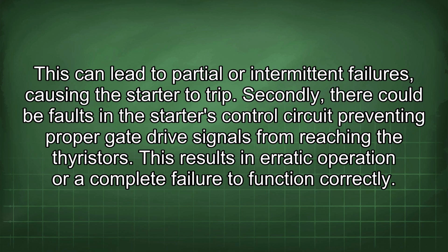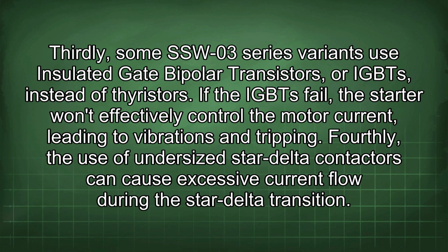Secondly, there could be faults in the starter's control circuit preventing proper gate drive signals from reaching the thyristors. This results in erratic operation or a complete failure to function correctly. Thirdly, some SSW-03 series variants use insulated gate bipolar transistors or IGBTs instead of thyristors. If the IGBTs fail, the starter won't effectively control the motor current, leading to vibrations and tripping.